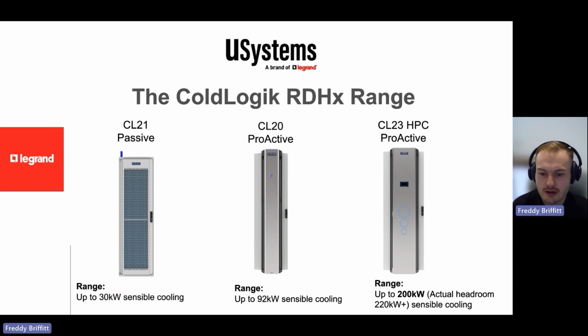So that's the central image and the image on the right-hand side of the screen. The CL20 is an active rear door. And by active, that means it has fans that pull the air over the coil itself. Now, the CL20 is capable of up to 92 kilowatts, and that's sensible cooling. So that's where our supply water is above 14 degrees, so we don't have to worry about humidity, sorry, condensation. And although it says 92 kilowatts, that's the max it can do.